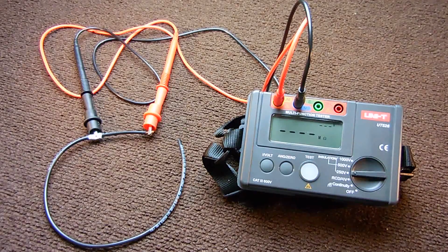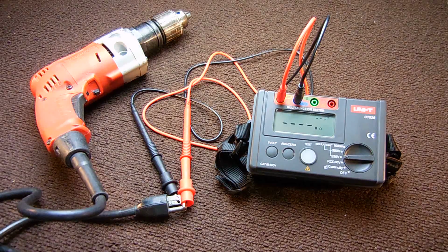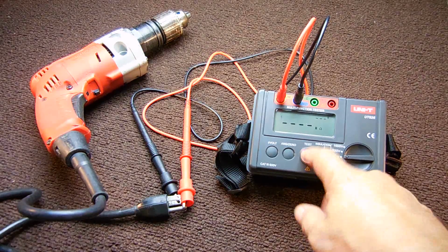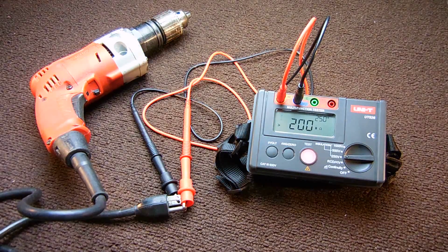Now let's take a look at the drill. Now we're going to test it on an electric motor. In this case, it's a drill. It could be a universal motor from a vacuum cleaner, compressor, electric motor for a swimming pool or a sprinkler system. Makes no difference. Just make sure you connect between the winding and the ground. I'm going to push the button. And that's over 200 megohm using 250 volts to test.